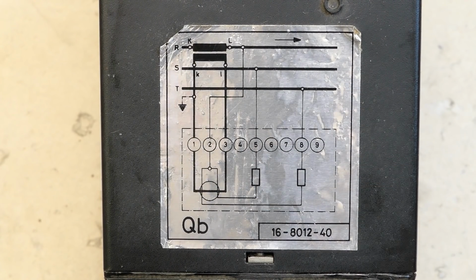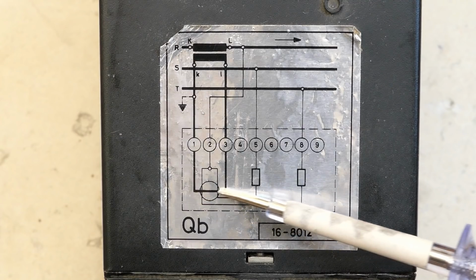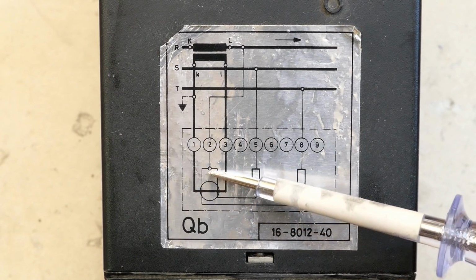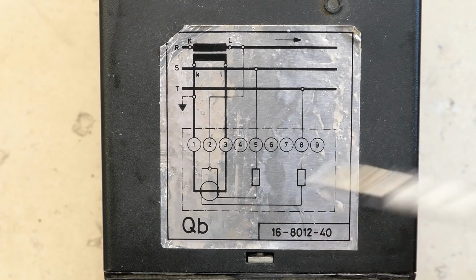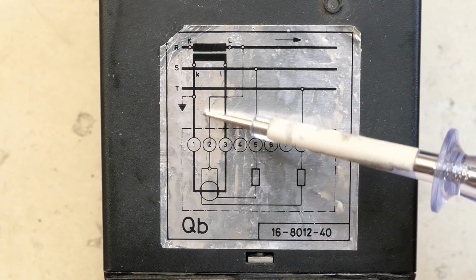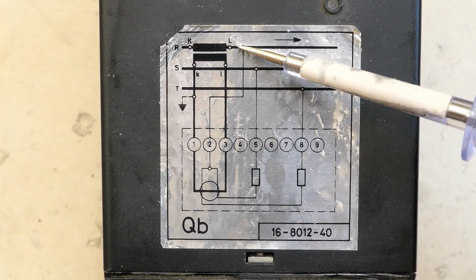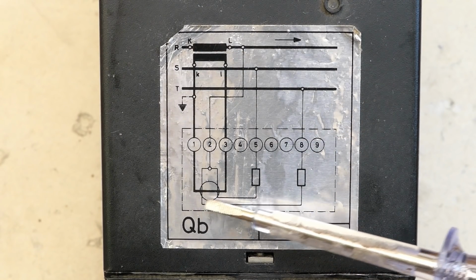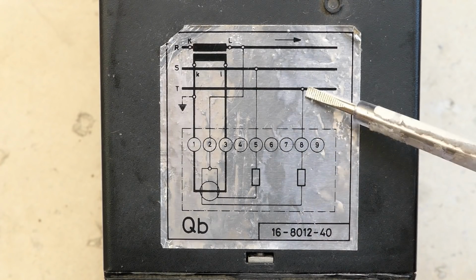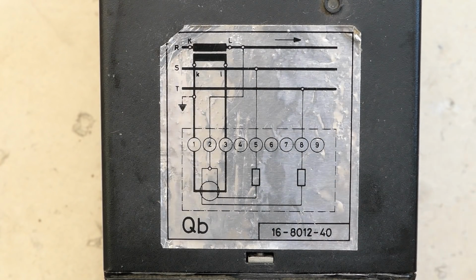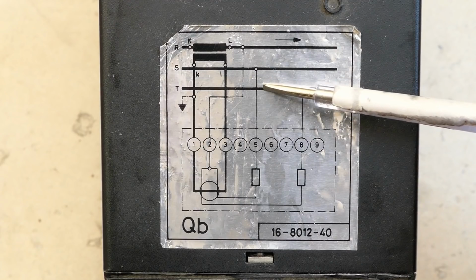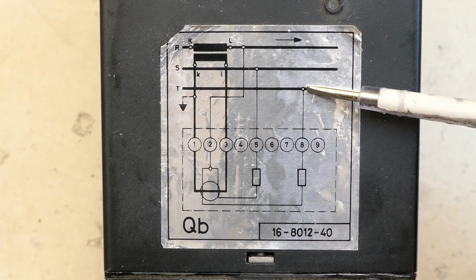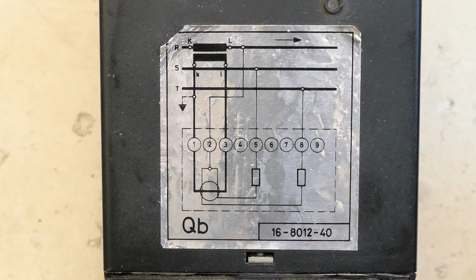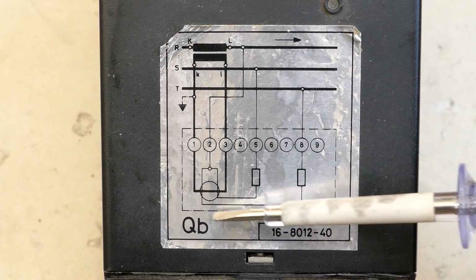5 amps. And here is the current sensing coil in the system and 2 voltage coils or reference coils, and the common terminal goes to the phase where the current is sensed, and the other 2 terminals of the voltage coils go to the other 2 phases via resistors. And in the other 2 phases it's not sensing the current, it's just using these phases as a phase reference, basically to get AC voltages with different phases.